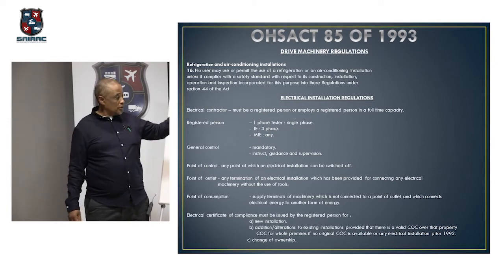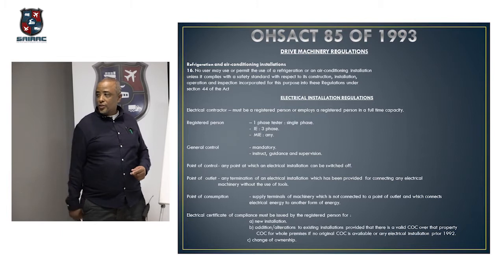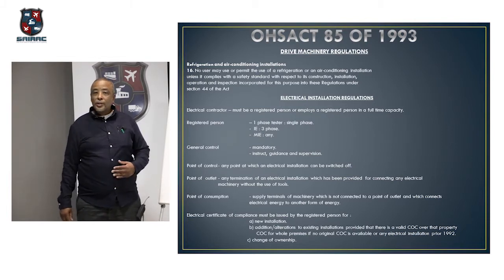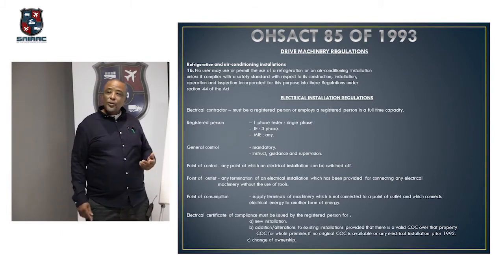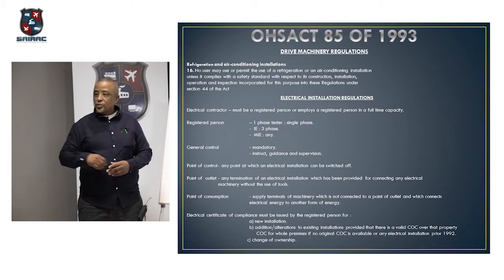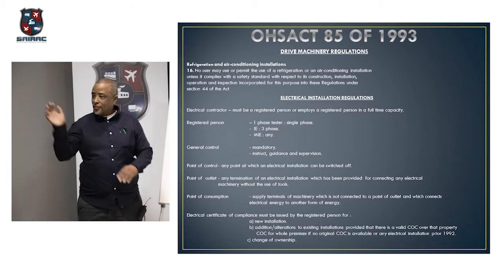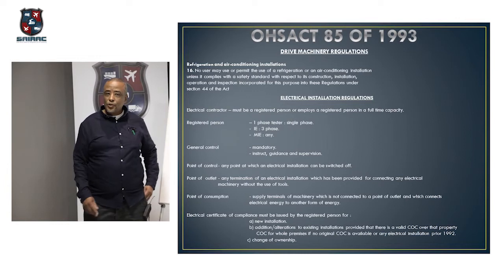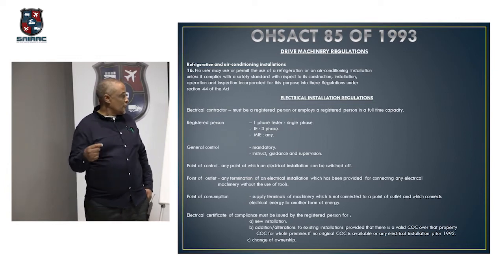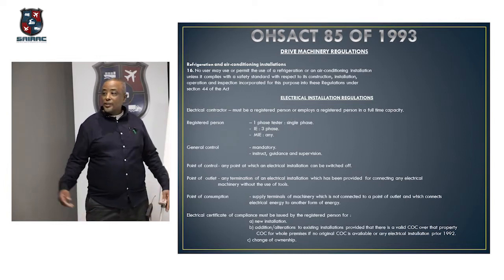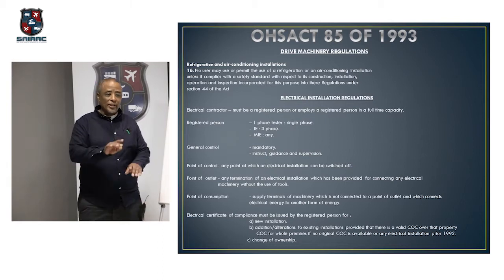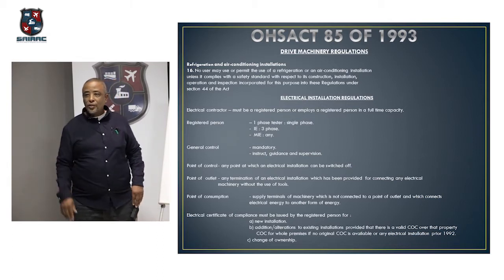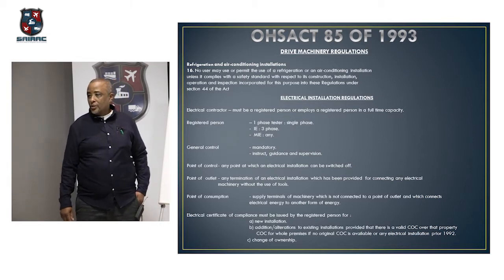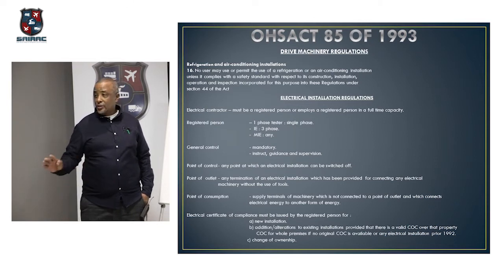We put the power on, you do your test, you're happy, you give us a COC on site. Okay, we normally recommend that they do all their tests, do your dead test, do your counts, everything else except when it comes to power. Then you can just fill that in and hand it over on site. Some guys say, well, okay, we left it in the bucket. Some guys say, no, we do it on the computer. Okay, then we'll give you a couple of hours. Okay, but we don't leave power on without a COC.